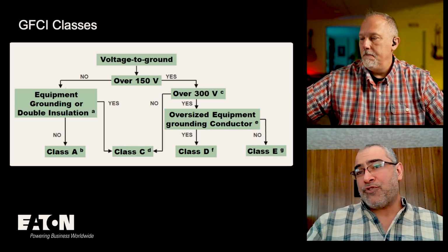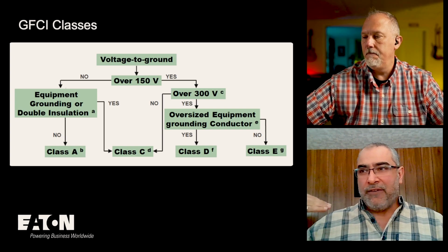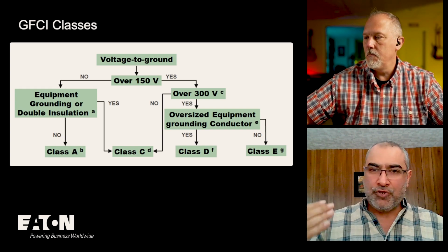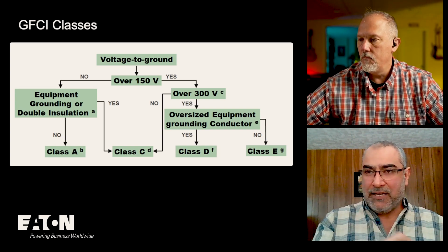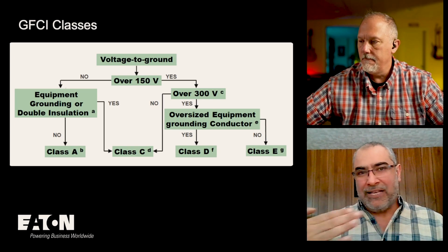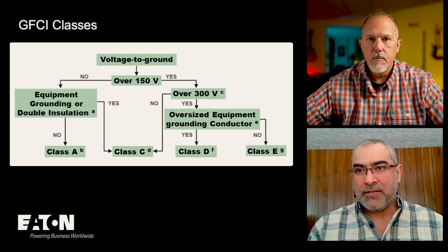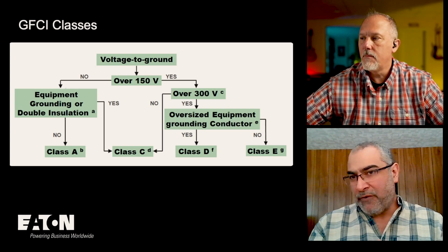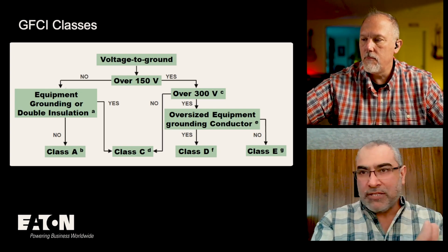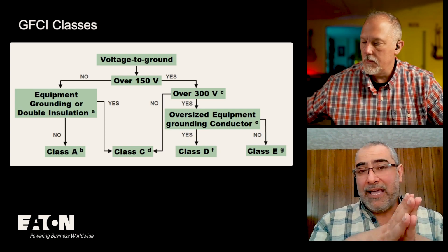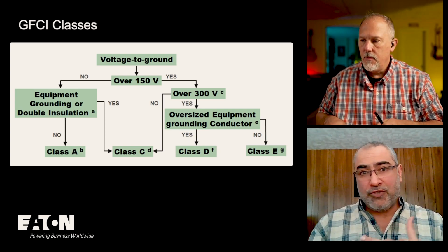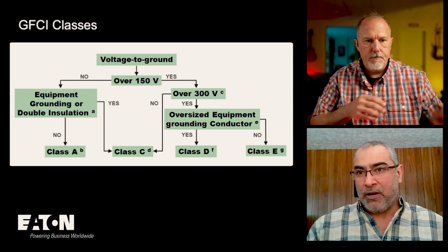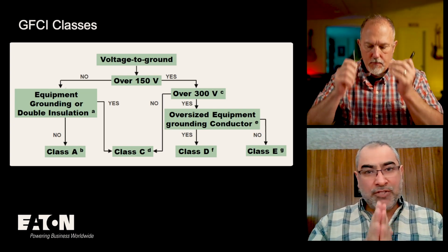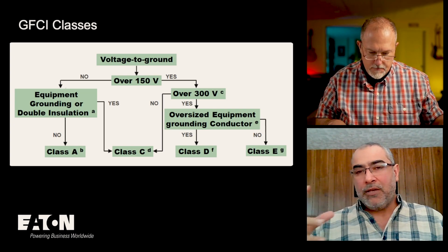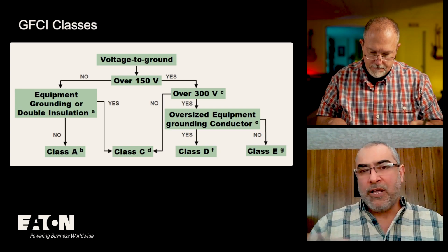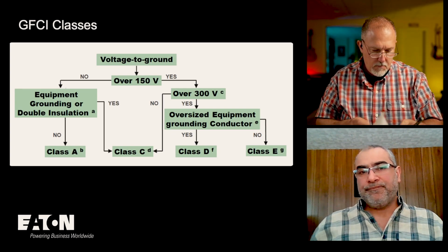This allows exactly what you're saying, Tom. If in your application the installer should be guided to install a Class C, you tell them install a Class C, don't tell them special purpose and leave them wondering which one. If they want a Class D for whatever reason, because of voltage levels, just tell them install a Class D. In the future, if UL decides to come up with a Class K or M or whatever, it's the same thing - just add the class, and we don't have to worry about special purpose versus normal, because at the end of the day they're GFCIs.